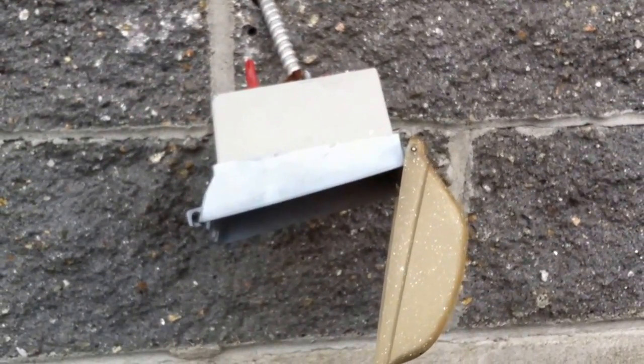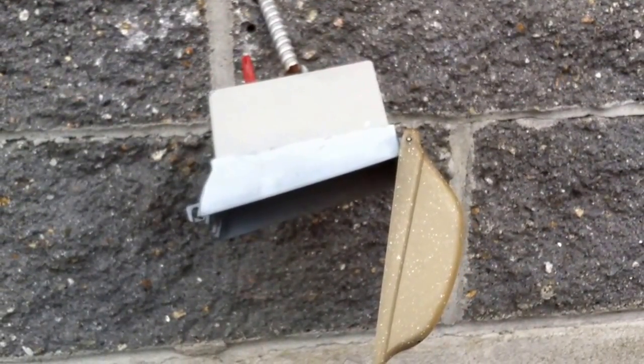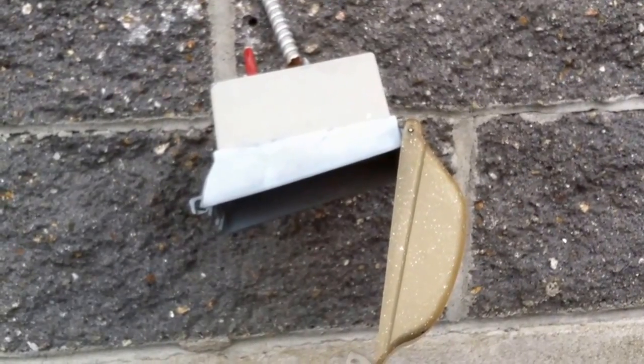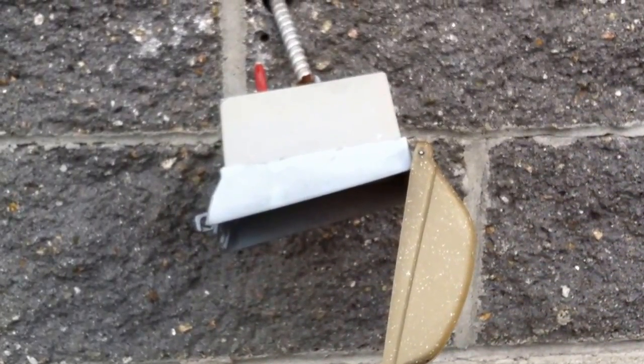This would be a violation of NEC section 314.23 which requires enclosures like this box to be securely fastened.